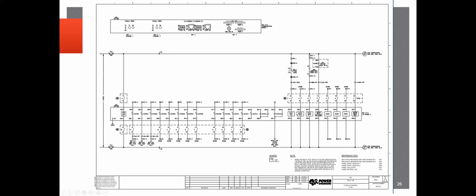So after your outputs, you'll move on to your inputs, which would just be all associated stuff that may be coming into the relay and may not necessarily have anything to do with the internal logic that could cause an inadvertent trip, but a lot of times there can be, especially with this 52A contact that could be coming from a different breaker. And if it sees that drop out at the incorrect time, then it could cause an inadvertent trip elsewhere. So outputs and then your inputs.